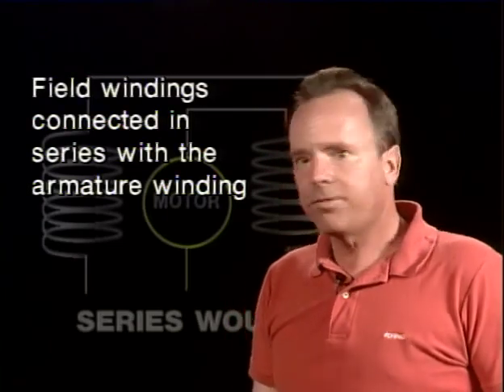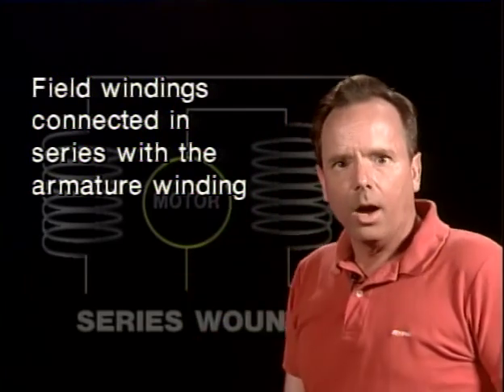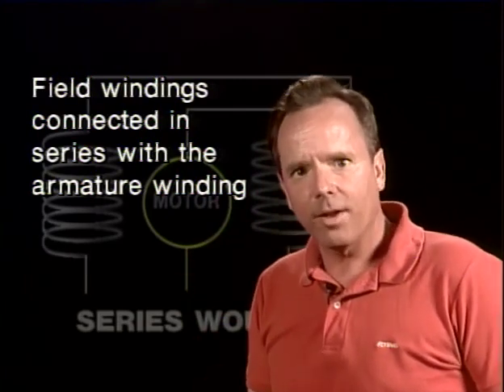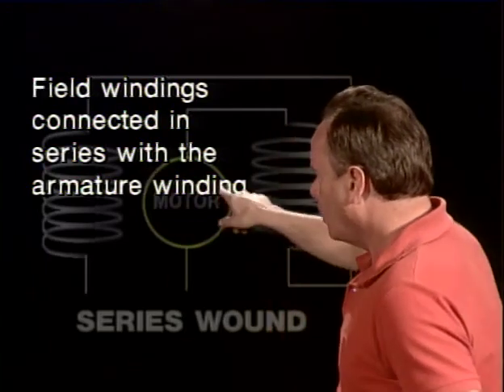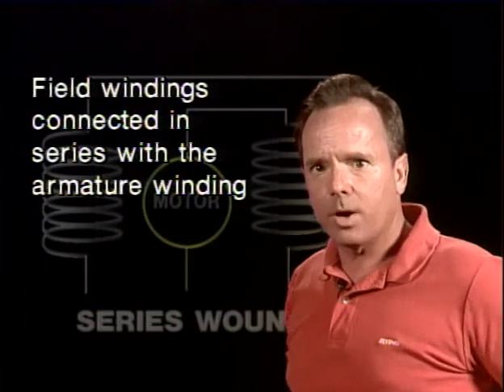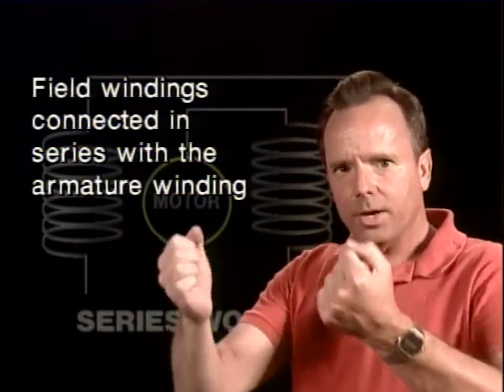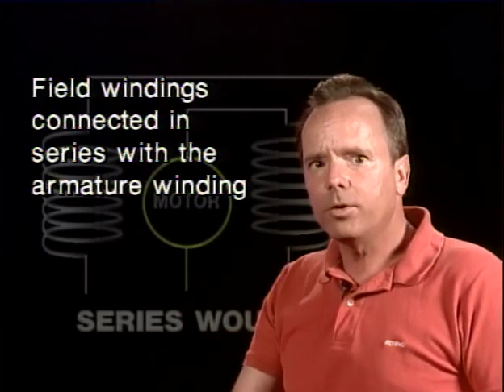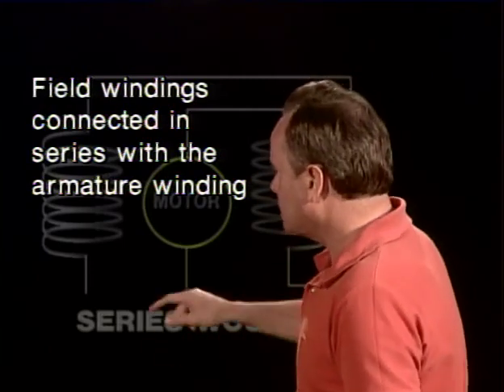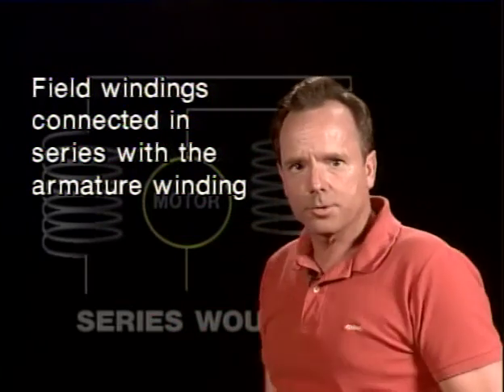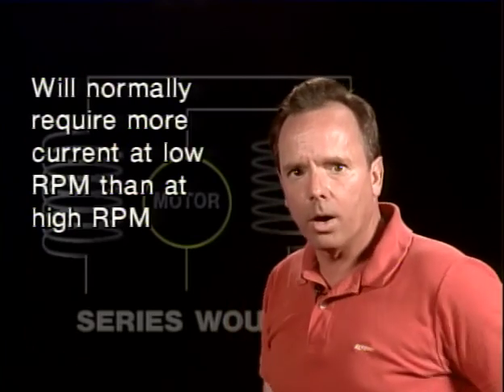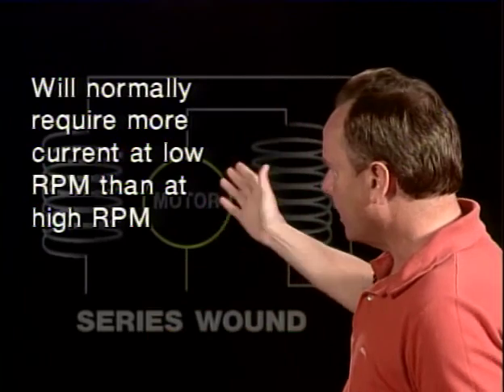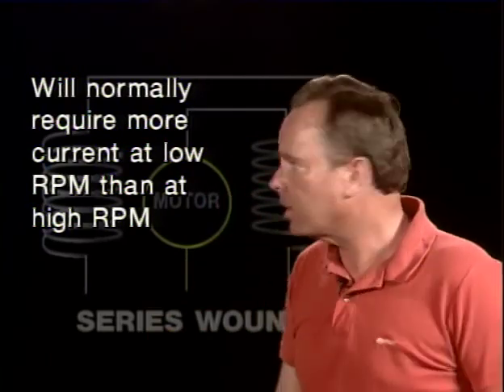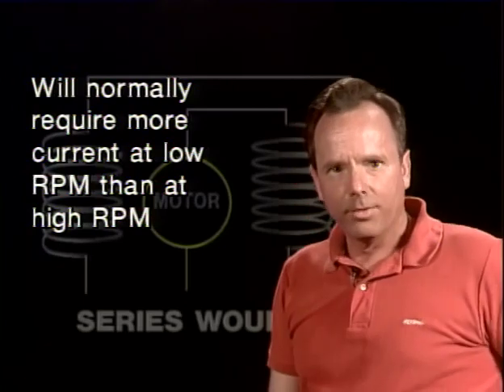Now let's take a look at something you need to know about a series wound motor, and that is the field windings. The windings in the field, and by the way, they consist of a relatively few turns of heavy wire, are connected in series with the armature winding. That is the purpose of a series wound motor. The field and the armature are in series with each other, and the field has relatively few turns of heavy wire in this particular case because all of the current going to the motor goes through the field. Now, the series wound DC motor will normally require more current at low RPM than at high RPM. That is one of the characteristics of a series wound DC motor: more current at low RPM than at high RPM.